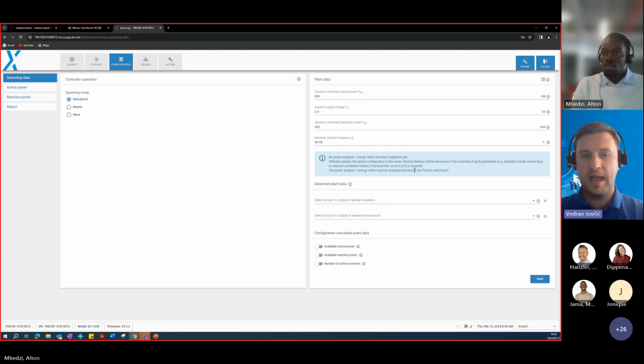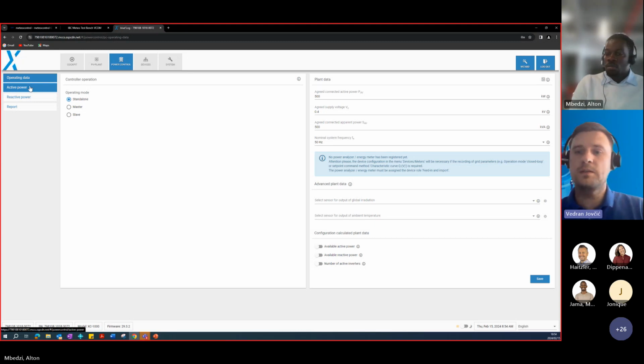There are updates - we have this new HEMS controller. This is an advantage when working with the blue log: you do not need new hardware. If you have a PV system only at the moment and want to operate power control with the blue log, you can install it and start with PV operation only. Maybe in the next months you decide to extend your PV system, add battery storage and also PV genset. Then you have a combined system with different types of devices. You can upgrade this software with the same hardware using the HEMS license. So you do not need additional hardware just because you are changing your system type from PV only to PV plus BSS - it's only a license upgrade, the so-called HEMS license.